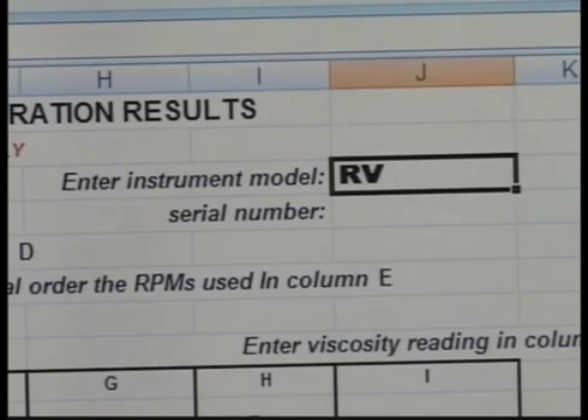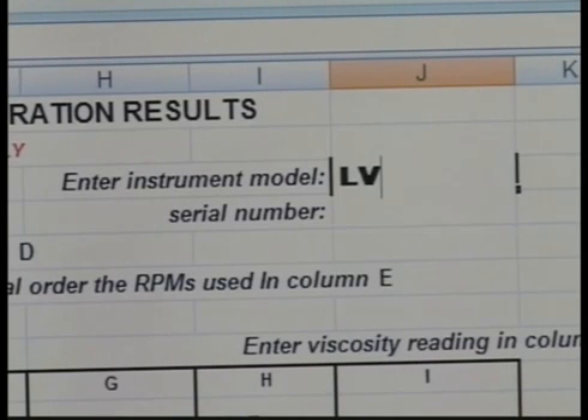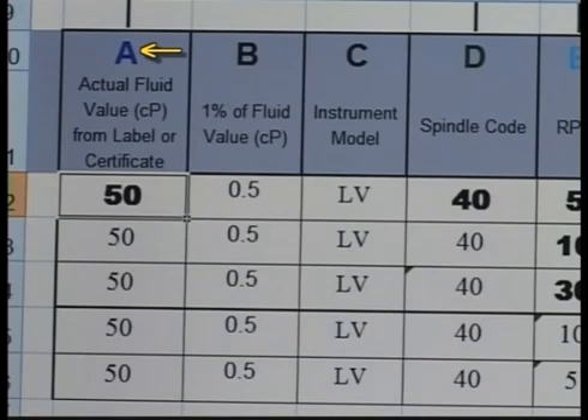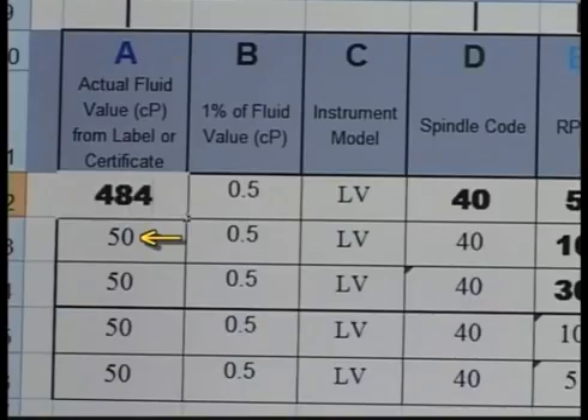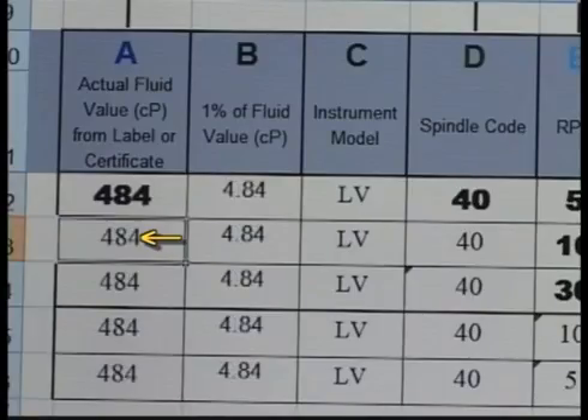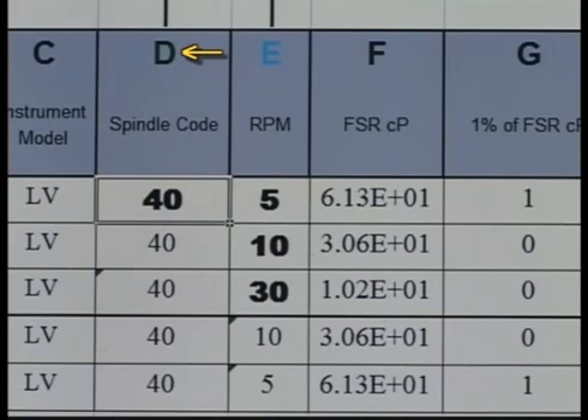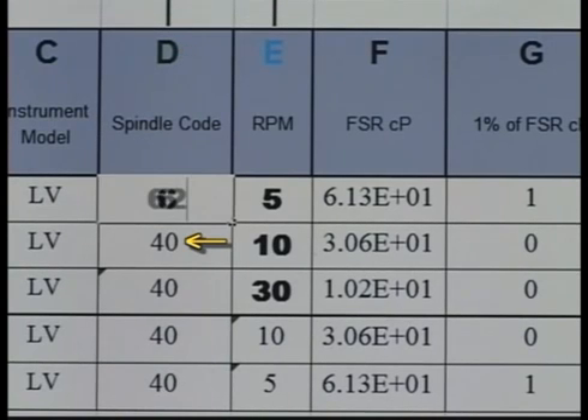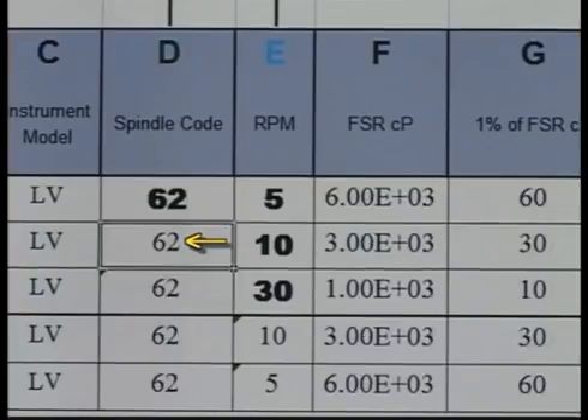Enter data in the bold fields. First, enter the spring torque of your instrument. In this case, this will be an LV. Enter the actual value of the fluid in column A. The remaining fields in this column will automatically update, as this value will not change. You can see the 1% fluid value column will update based on this entry. This is the accuracy of the fluid. Enter the spindle code in column D. Again, the fields in this column will automatically update.